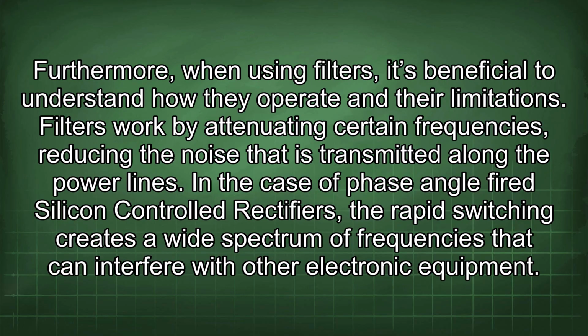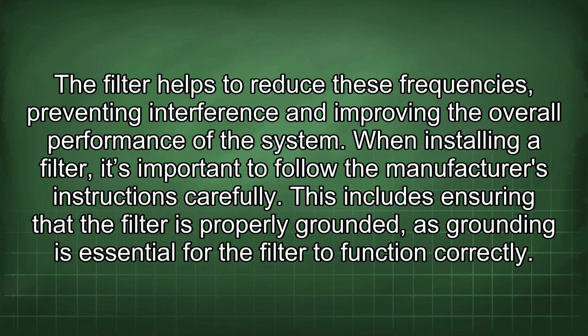Furthermore, when using filters, it's beneficial to understand how they operate and their limitations. Filters work by attenuating certain frequencies, reducing the noise that is transmitted along the power lines. In the case of phase angle-fired silicon-controlled rectifiers, the rapid switching creates a wide spectrum of frequencies that can interfere with other electronic equipment. The filter helps to reduce these frequencies, preventing interference and improving the overall performance of the system. When installing a filter, it's important to follow the manufacturer's instructions carefully.